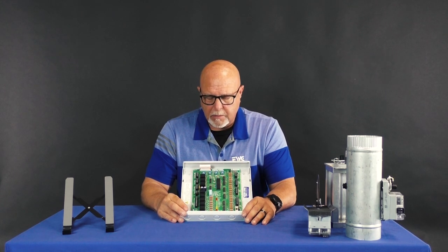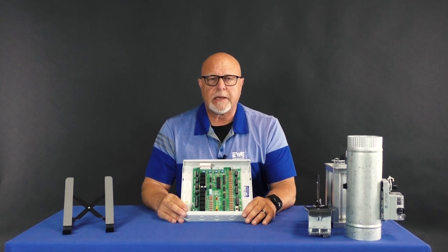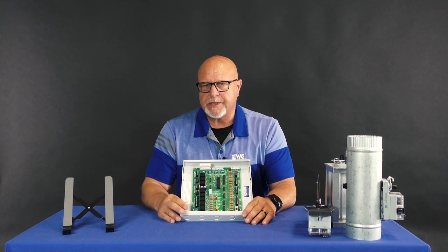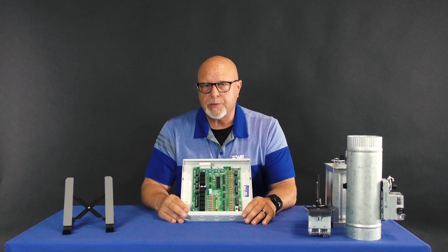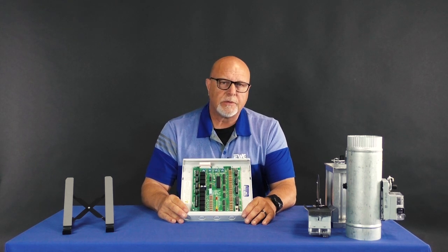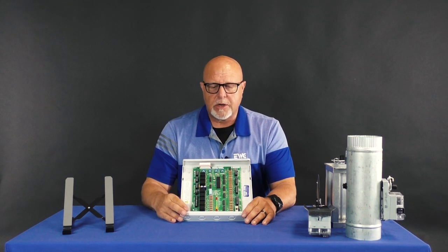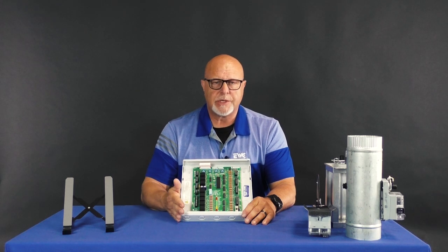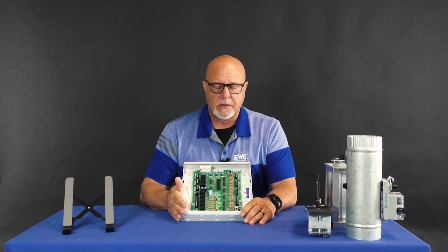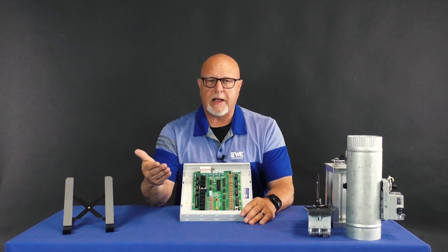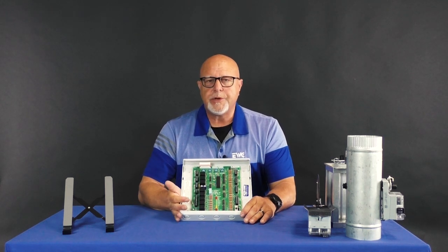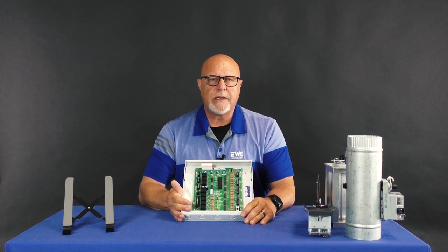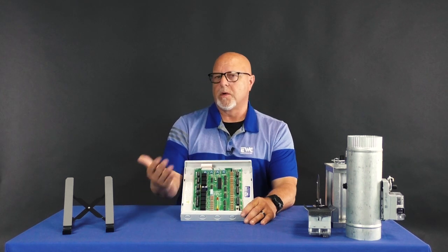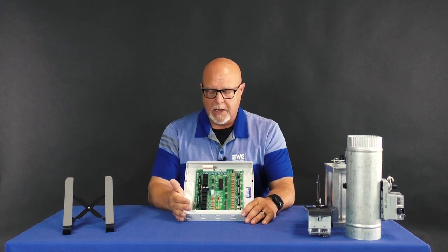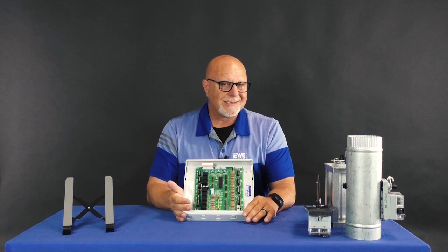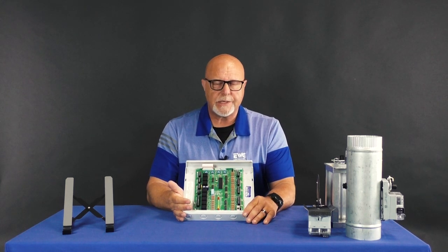This board makes it very user-friendly in the fact that 95% of any zoning job that you would go to, this board would be able to handle it. If you need a 3 zone, this out of the box will do the job. A BM Plus 5000 is able to handle your 4 and 5 zones. Very seldom will you get over 5 zones, but in the event that you need a 6 or 7 zone, order that BM Plus 7000 and take care of those 6 and 7 zone jobs that you would walk into.